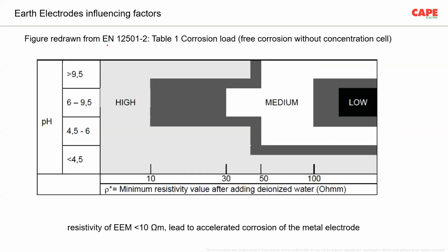I took this table from EN 12501 part 2, which is talking about the corrosion factors and the pH values. Here you can see the resistivity of the soil, or any kind of material which is in and around the earth electrode. If the resistivity is less than 10 ohm meter, it is more corrosive.